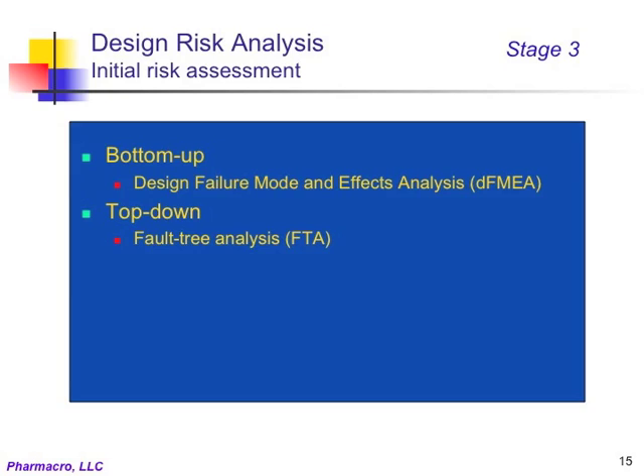Likewise, the top-down process asks the following question: what kind of failures can occur at the system level? This is then traced down to the subassembly and to the component level to identify the possible cause and the risk associated with the failure. The risks are then mitigated through design modification or by developing unambiguous instructions for use.